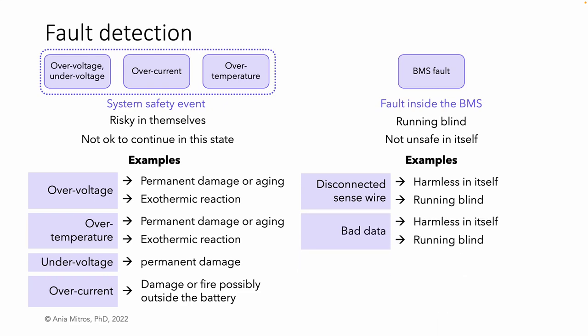Many types of faults can cause bad data. A flipped memory bit, a damaged ADC, or electrostatic damage to a pin on the measurement chip are three examples of single-point faults that can lead to bad measurements. For each of these, a diagnostic is possible to determine that something is not right, to allow the BMS to raise a flag. Again, these are all harmless in themselves, but leave the BMS running blind or partly blind.